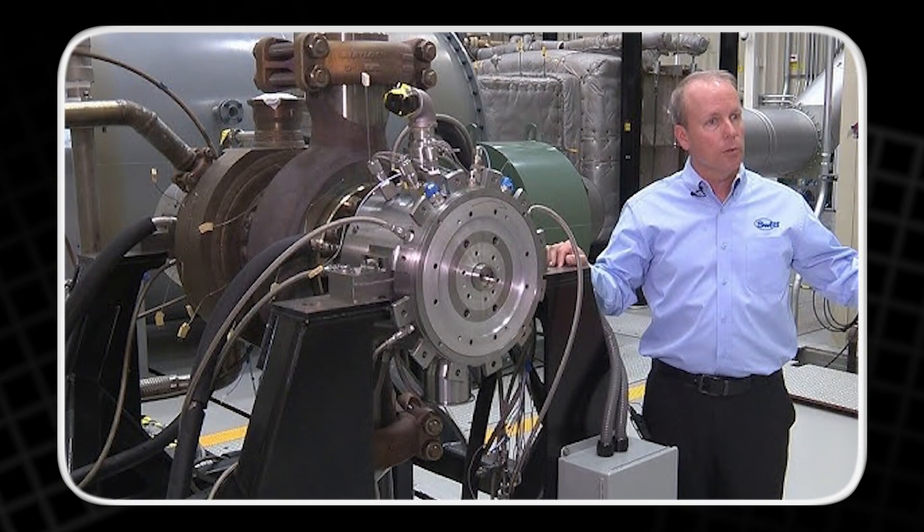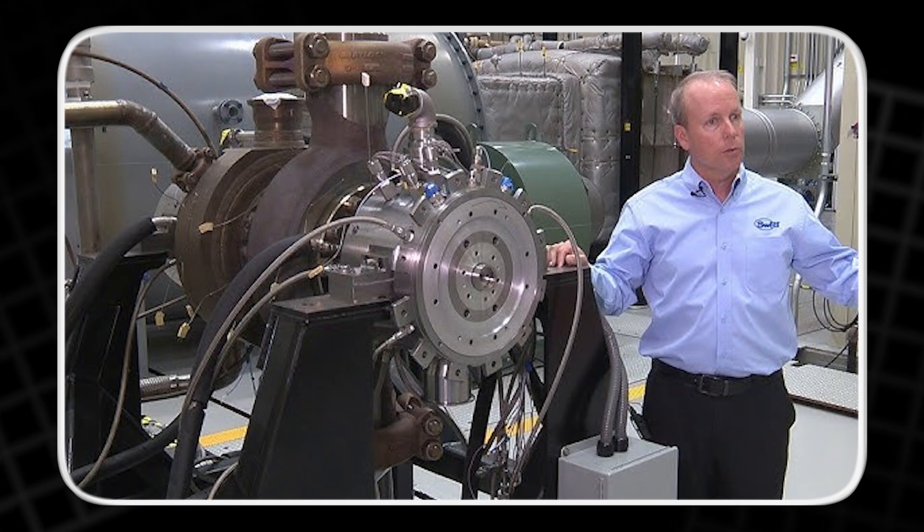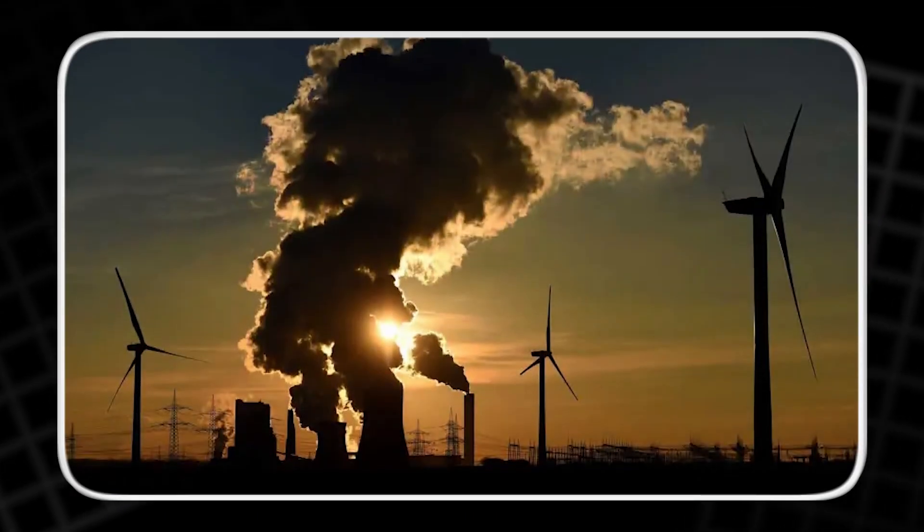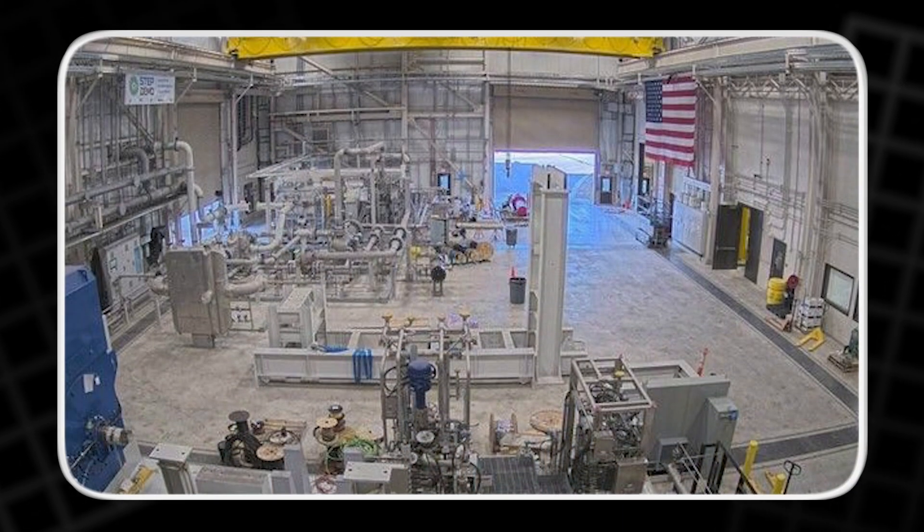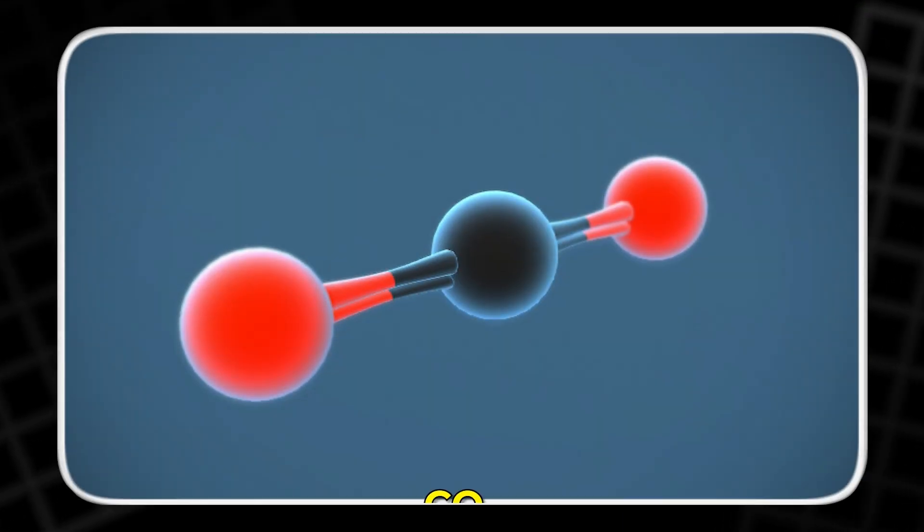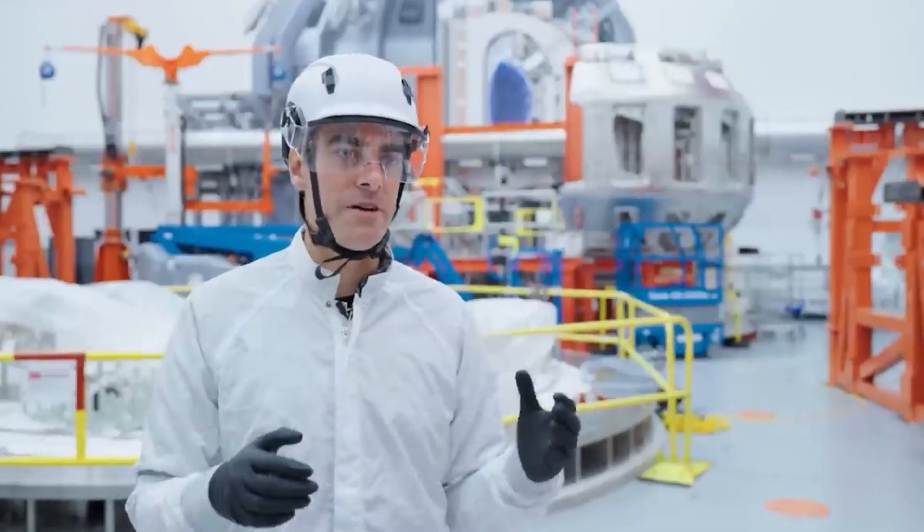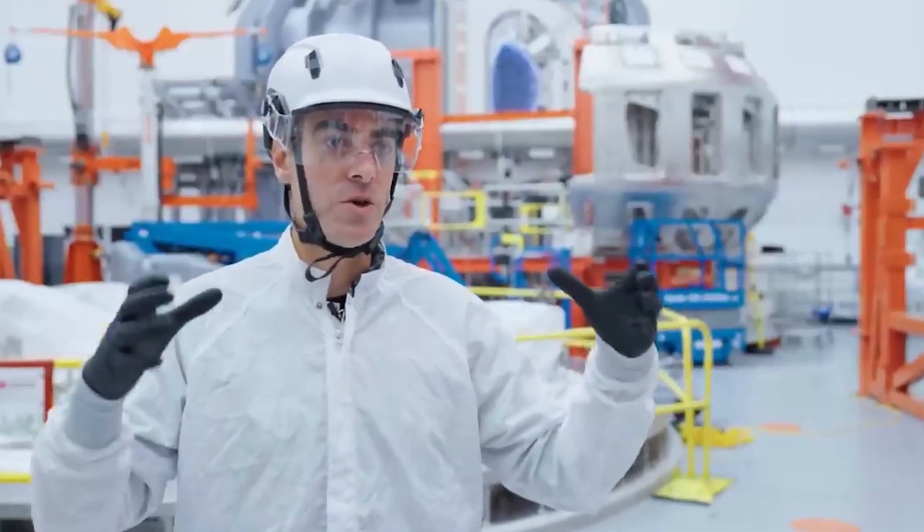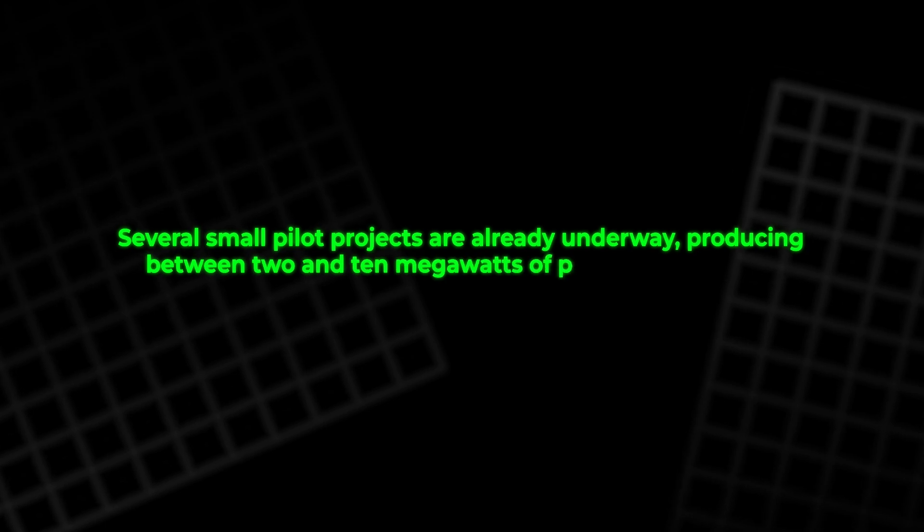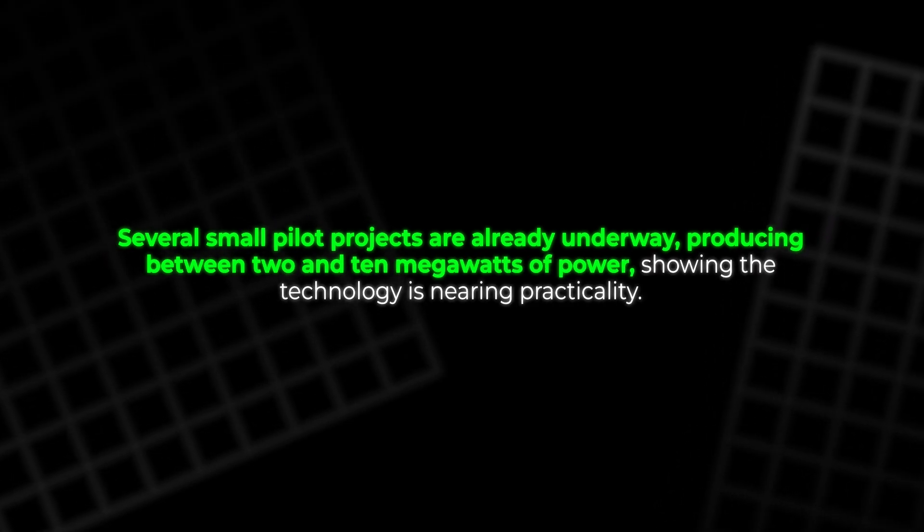A related idea is oxycombustion: burning natural gas with pure oxygen instead of air. This produces a concentrated exhaust of carbon dioxide and water vapor, making it easy to capture and store emissions. However, CO2 at high temperatures can corrode turbine components. Engineers are developing new nickel-based super-alloys and thermal barrier coatings to combat this. Several small pilot projects are already underway, producing between 2 and 10 megawatts of power, showing the technology is nearing practicality.